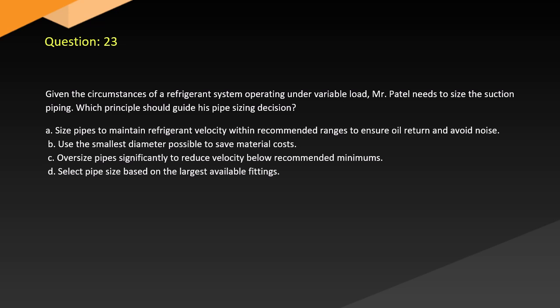Question 23. Given the circumstances of a refrigerant system operating under variable load, Mr. Patel needs to size the suction piping. Which principle should guide his pipe sizing decision? A. Size pipes to maintain refrigerant velocity within recommended ranges to ensure oil return and avoid noise. B. Use the smallest diameter possible to save material costs. C. Oversize pipes significantly to reduce velocity below recommended minimums. D. Select pipe size based on the largest available fittings.